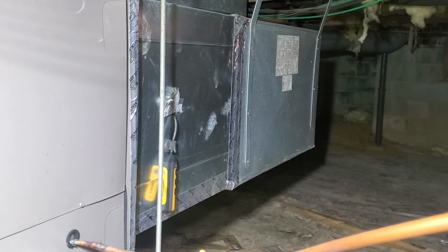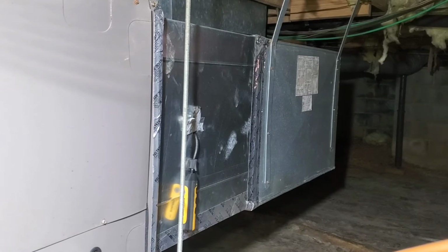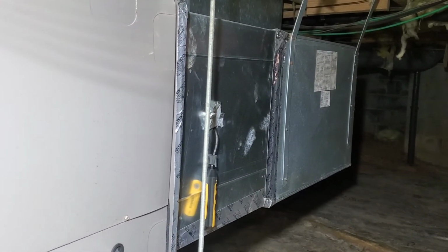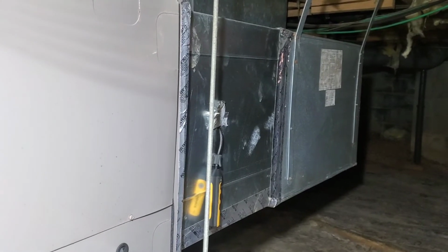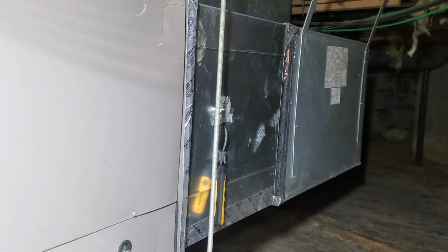Now we need to be very careful that we're not too close to the indoor coil where we could be measuring radiant heat. I've played around with this a lot. I really don't see that very often. If you're taking it at a furnace, and yeah, don't be too close to the heat exchanger, because that heat exchanger is like 4,000 degrees. But when you're working on a heat pump, you're measuring supply air temperature.